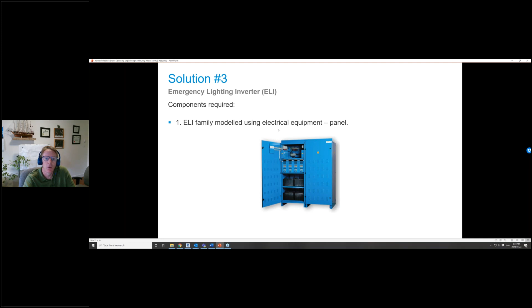Now, when you're designing with an ELI, you need to pay attention to how loaded you are. You can't exceed the runtime ratings of the emergency lighting inverter. As I mentioned, often we like to drive a little panel board, which then drives our individual lighting circuits. We typically pick up every second light.